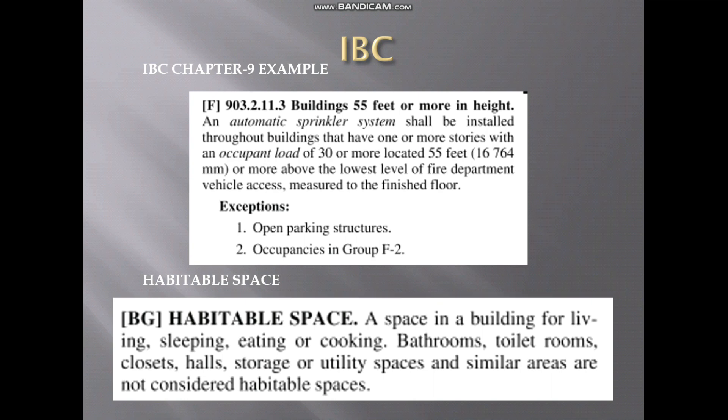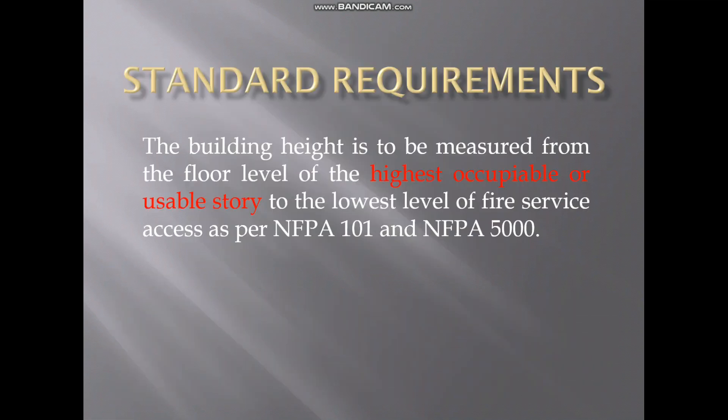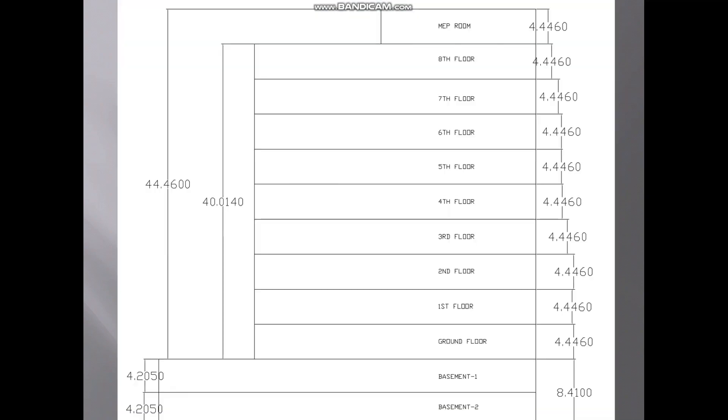So we need to decide and see the standard requirement to finalize this. The building height is to be measured from the floor level of the highest occupable or usable story to the lowest level of fire service access, as per NFPA 101 and NFPA 5000.